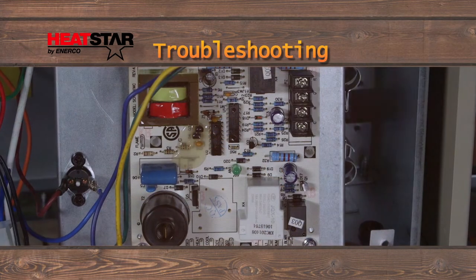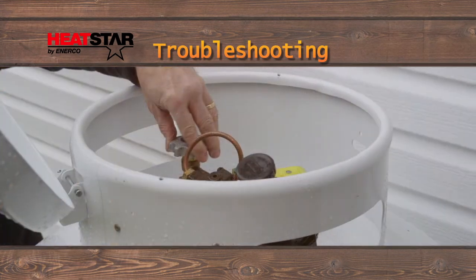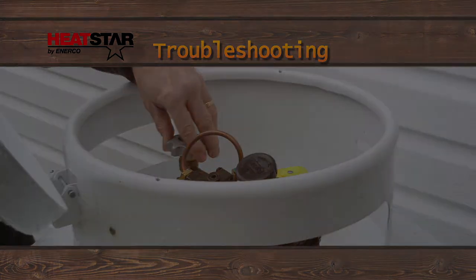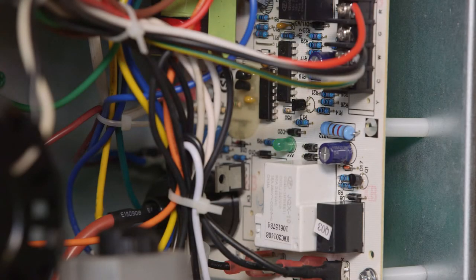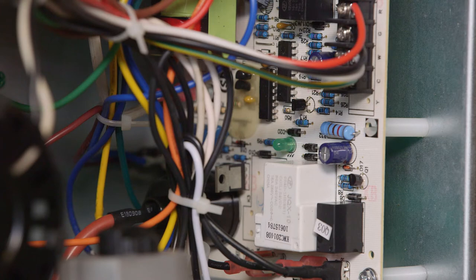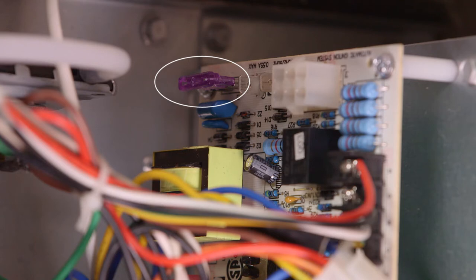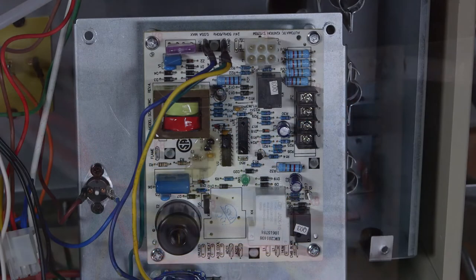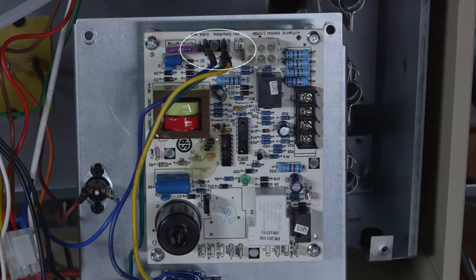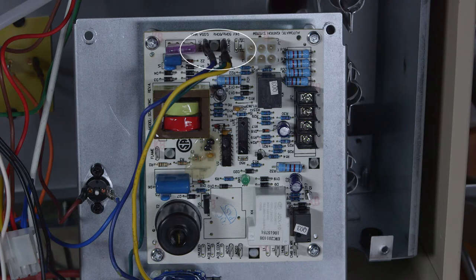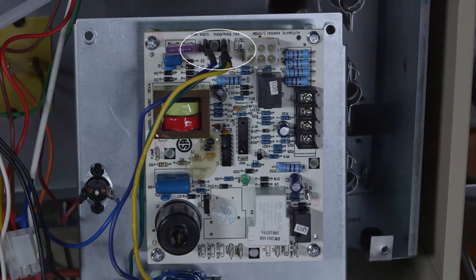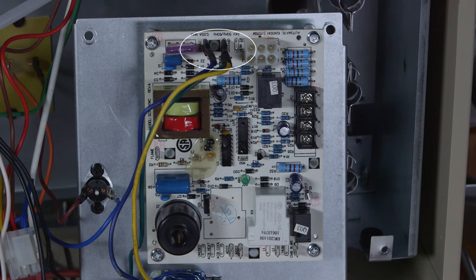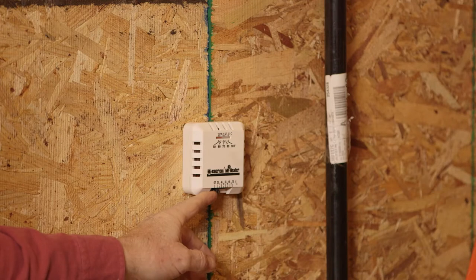Troubleshooting. If the unit fails to operate, check the following. Is the green LED on and flashing on the circuit board? If the LED does not light, check the 3 amp fuse in the top left corner of the circuit board. If the fuse is okay, check the main power to the unit, power wire connections and 24 volt AC from a transformer to the board. Is the thermostat calling for heat?